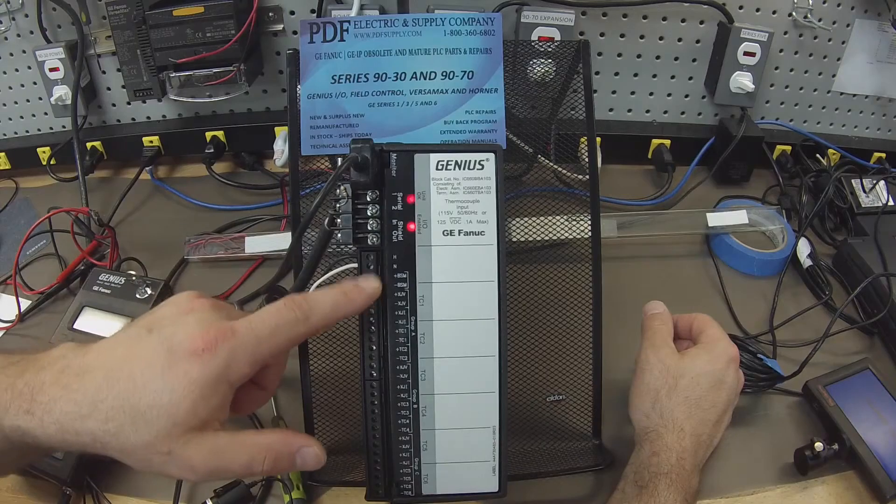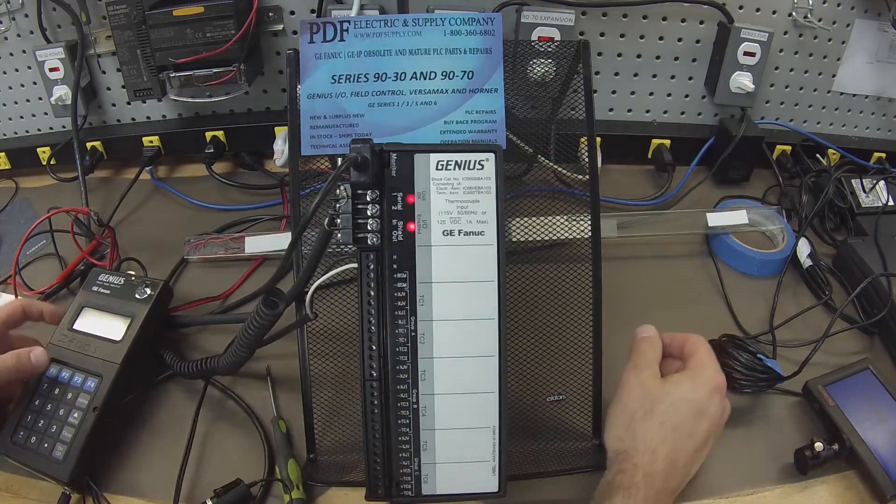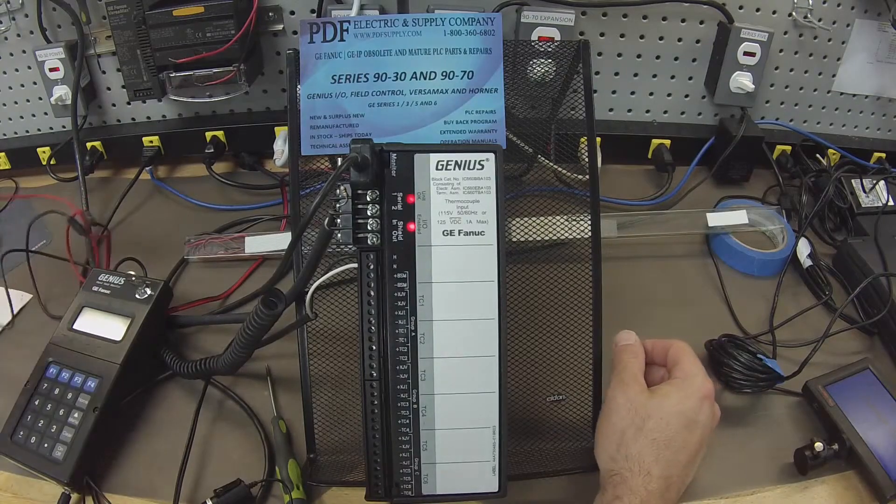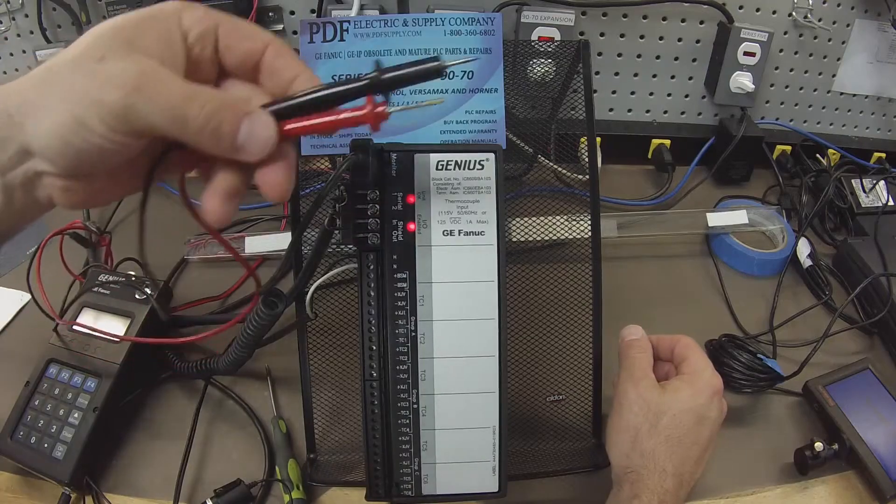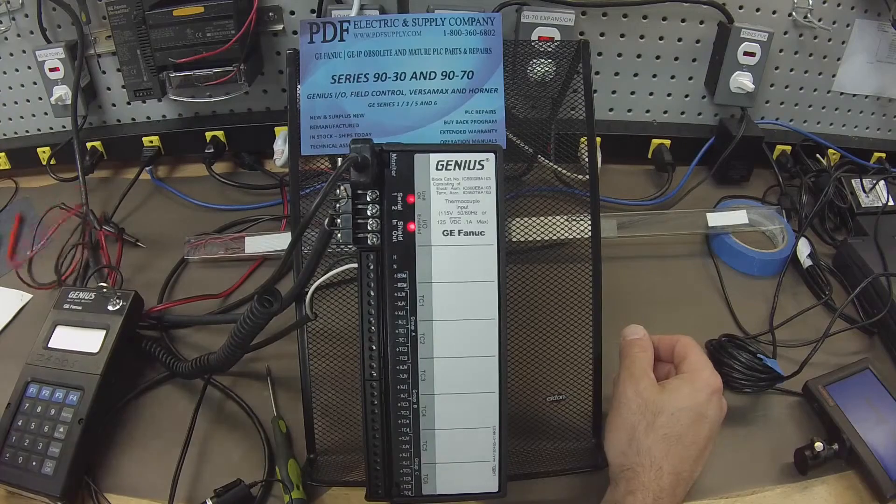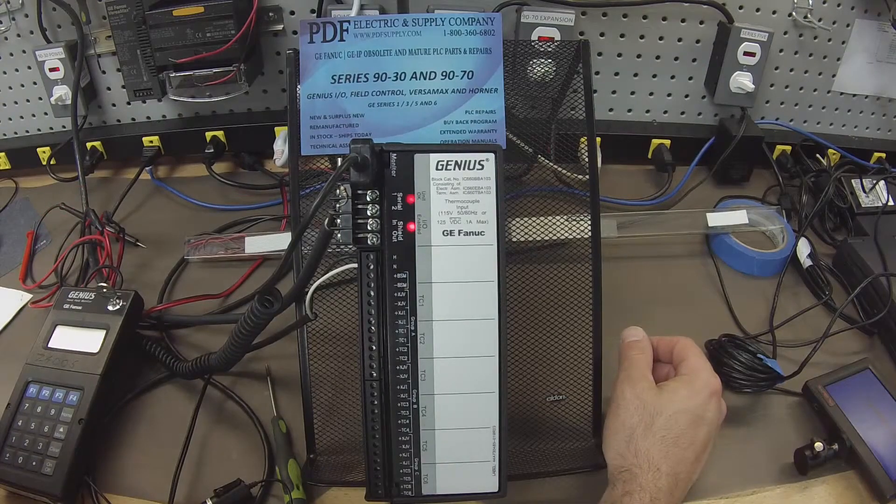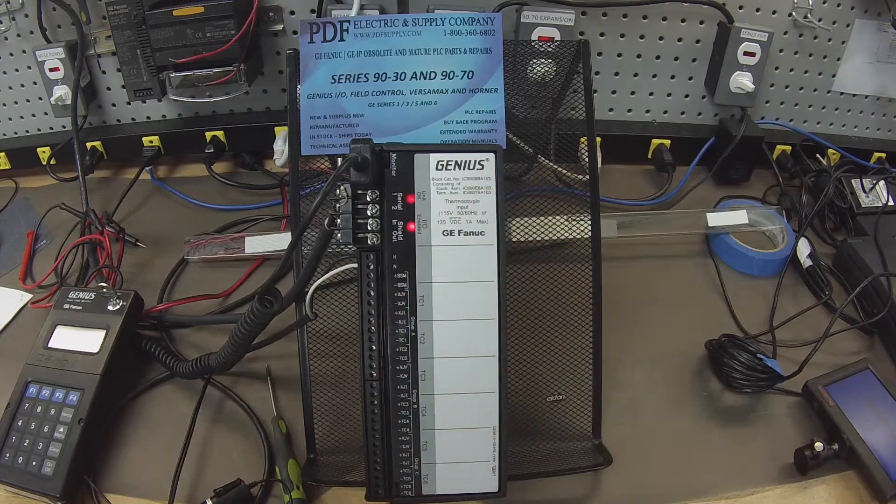So the next things we want to check, of course, are the inputs, thermocouple 1 through 6. Now, I have as a test fixture a thermocouple with positive and negative leads for the two different types of metals. It's a J-couple and it creates a millivolt-type signal which can be read by the IC-660BBA-103.